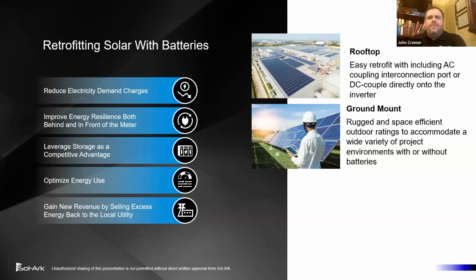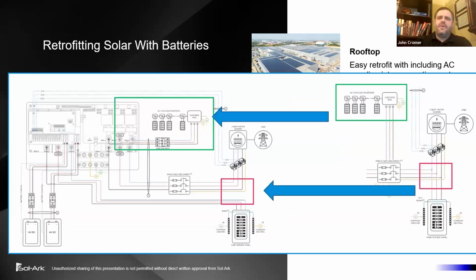So let's start out with one of my favorite applications. Certainly a popular application is retrofitting existing solar power with batteries with Sol-Ark. The way that you would do that is, traditionally with commercial solar, that solar array is tied in as a line side or supply side tap, perhaps at the utility transformer, and you would essentially unwire that tap and put the inverter in line. You would take your AC coupled solar conductors and just land them on the inverter on the gen port. So instead of connecting a generator with AC coupled solar, you just land the AC coupled solar array directly onto the Sol-Ark inverter.